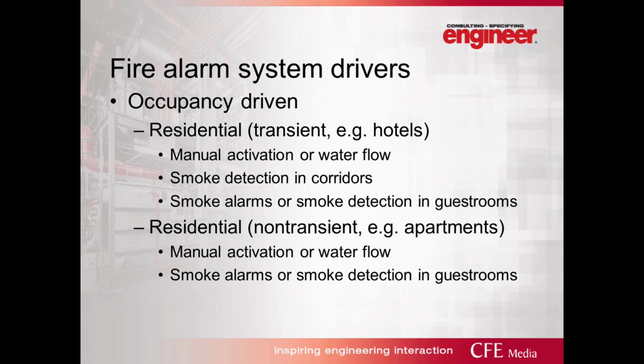Residential occupancy. There are some differences between apartments and hotels. Apartments being a non-transient occupancy and hotels being transient occupancies. Now, sometimes there's a gray area between the two. We're seeing some very large apartment buildings that are getting temporary hotel uses within them. So there has to be some modifications to the base building fire alarm to accommodate those uses.